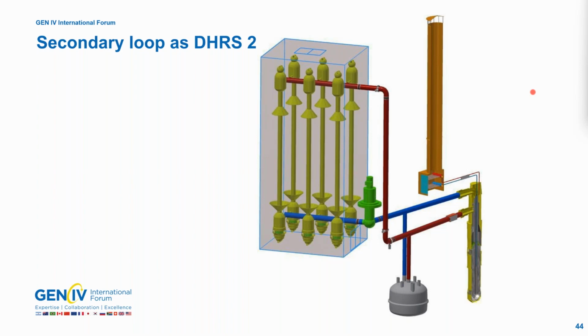That is a view of the secondary loop at the DHRS2. We see the heat exchanger is there. That is the DHRS1, that we will speak about after. For the DHRS2, we see that the sodium is going into the 6 modules and comes back. And so if you open the straps in this part and in the upper part, there is natural convection of the air through the casing. And as on the Phoenix reactor, you cool the reactor easily by natural convection.